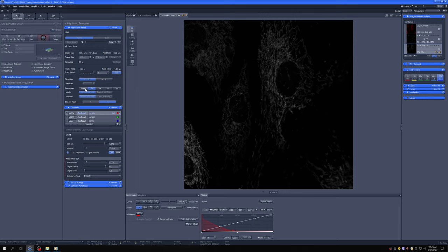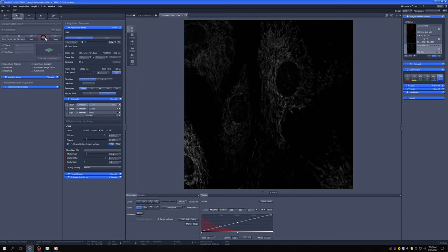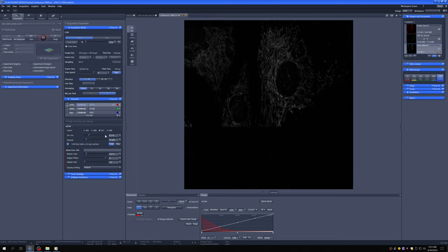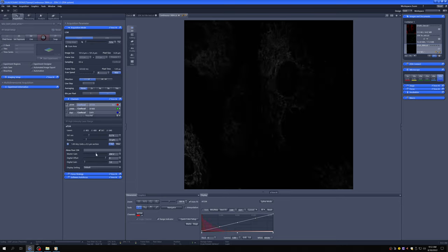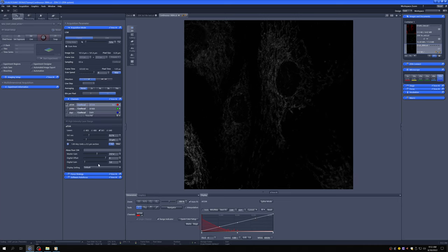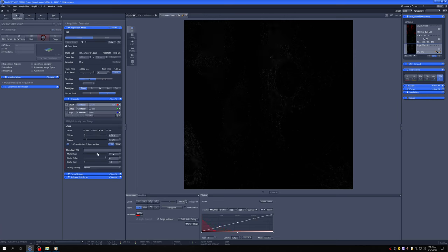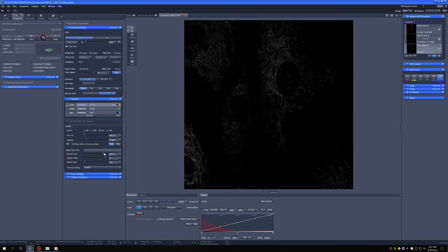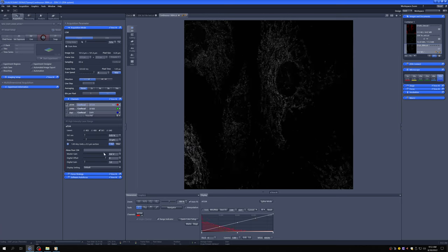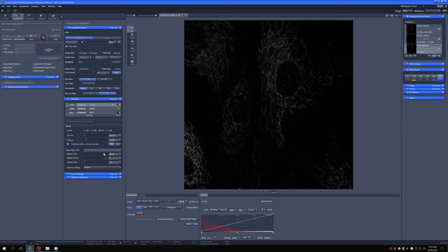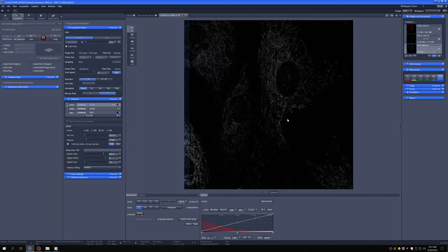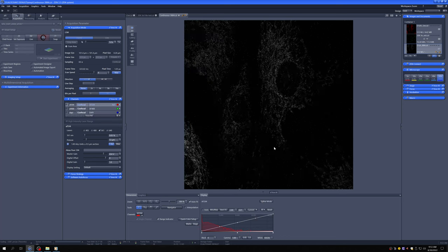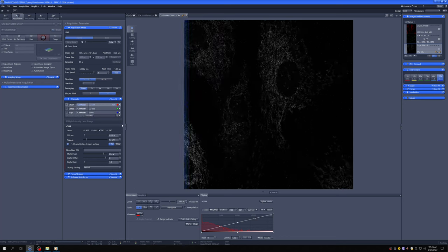Let me actually, on purpose, make the initial image worse so that you can actually see the effect of averaging. I'm going to reduce the laser power by a lot to 0.2%. I'm going to increase the gain to get a much noisier image. I'm going to do that even more because I really want you to see the effect of averaging. Now we have kind of a very, very noisy image because I want to show you the effect of averaging.